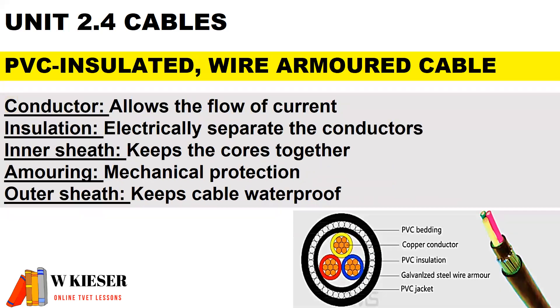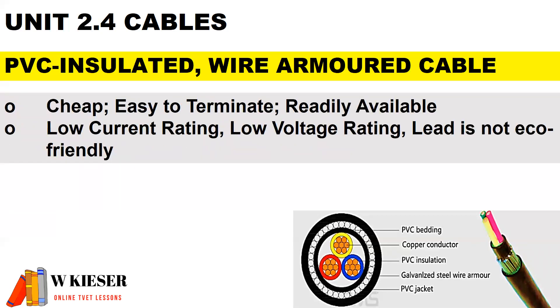For a PVC insulated wire armoured cable, there are different components. The conductor itself allows for the flow of current. The insulation electrically separates the conductors. The inner sheath keeps the cores together. The armoring provides mechanical protection, and the outer sheath keeps the cable waterproof. The advantages are: it is cheap, easy to terminate, and readily available.